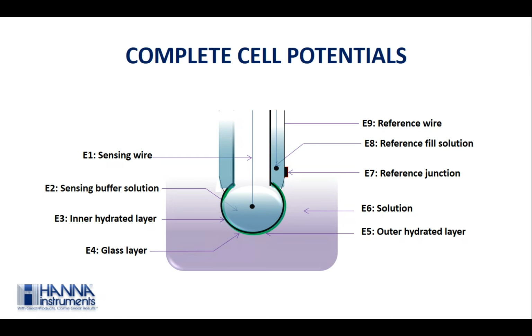Other than these components, there are an outer hydrated layer and an inner hydrated layer as part of the cell potential. In acidic solution, H+ ions diffuse in the outer hydrated layer and a positive charge is established, whereas in alkaline solution, H+ ions diffuse out of the hydrated layer and give a negative charge. This is how the electrode identifies whether a solution is acidic or alkaline. If a solution is alkaline, a negative charge is developed, or you get negative millivolts, and if the solution is acidic, you get positive millivolts. These hydrated layers limit the diffusion of hydrogen ions according to the pH of the solution. If there is any disturbance in these two hydrated layers, the user might observe fluctuation in the readings.